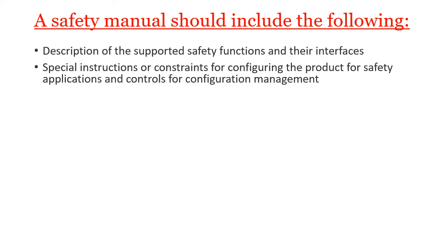In other cases, there are transmitters which drive low or high depending on the fault condition. Now, your safety system may have a requirement of output going high. Another safety system may have a requirement of output going low in case of the fault condition. So you need to configure that. Only if you configure that, then your safety action will be in place. Otherwise, the safety action will be void. So this is the meaning of the second line.